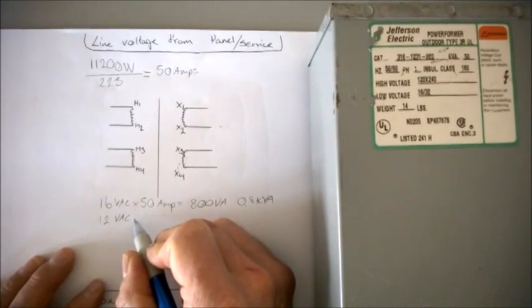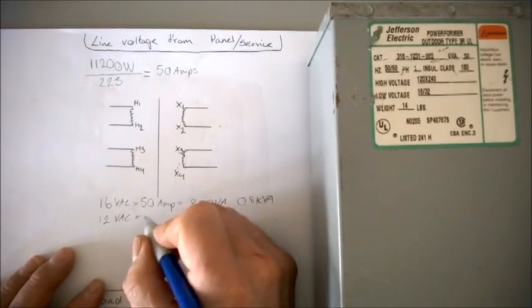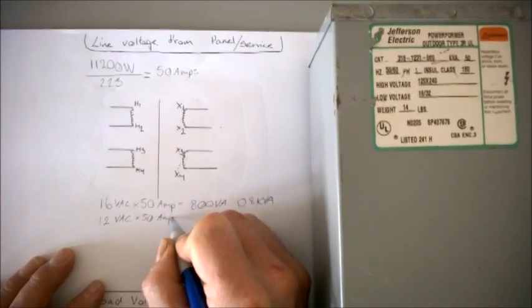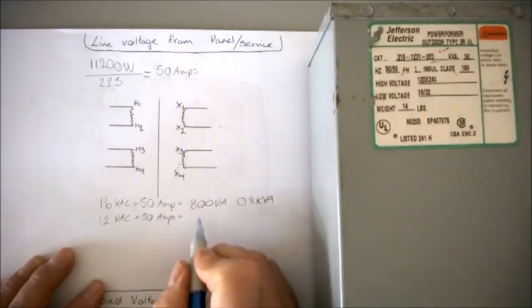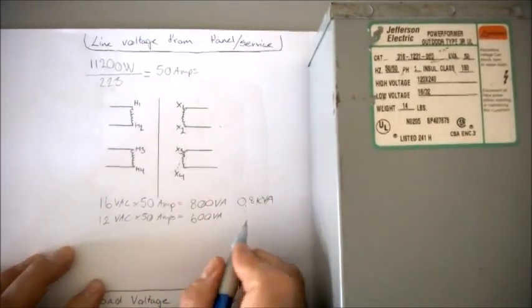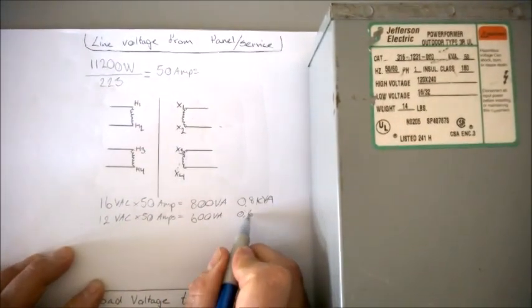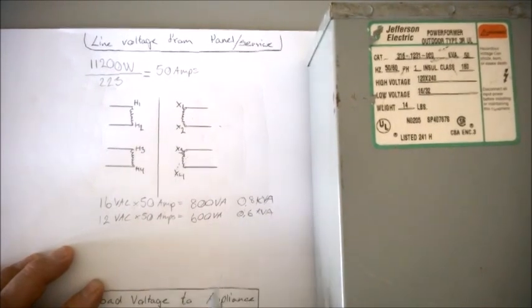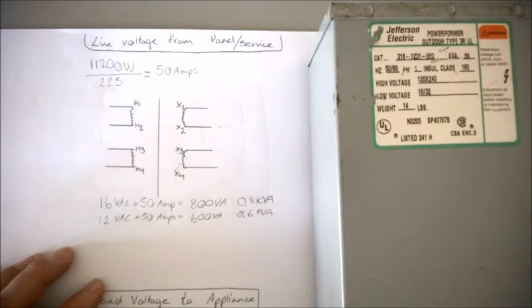Most of you probably already figured this one out, but let's see here. With 50 amp load, 600 VA. So that's a 0.6 KVA. So now we're able to put that down to a 0.75 by lowering how much we want to boost the voltage with.